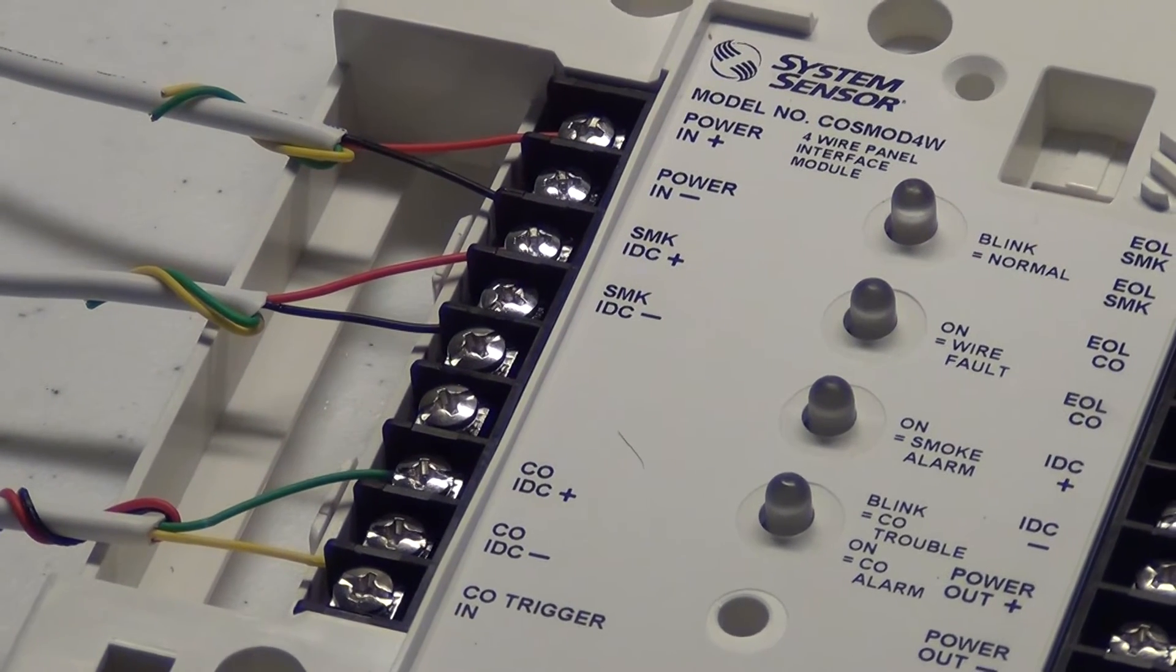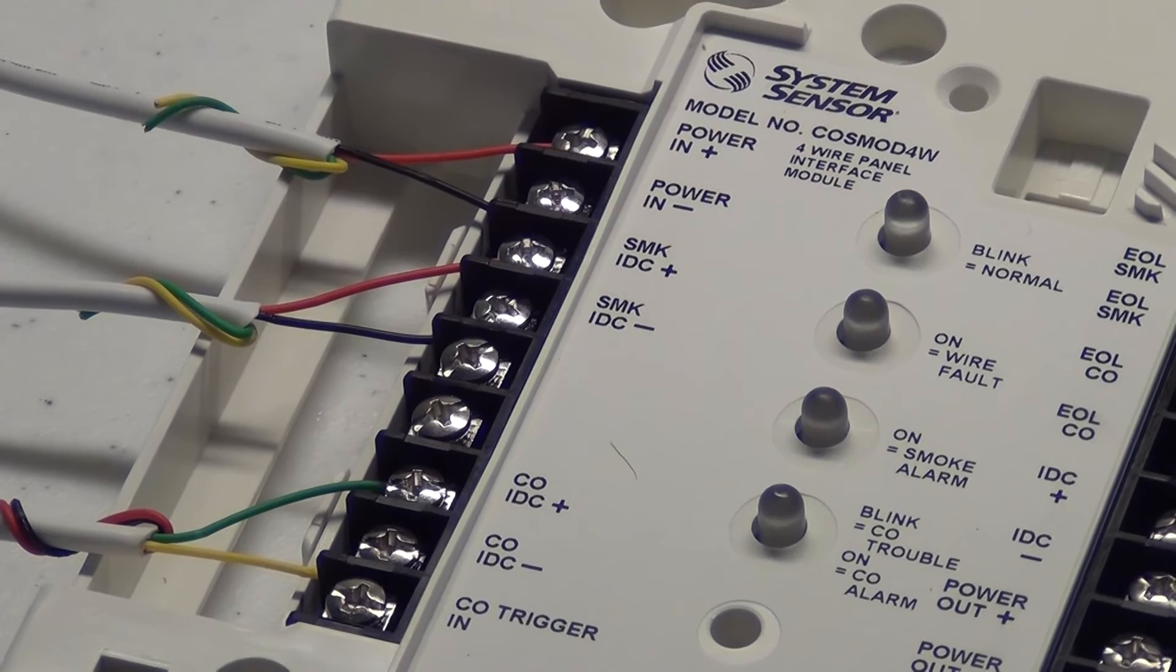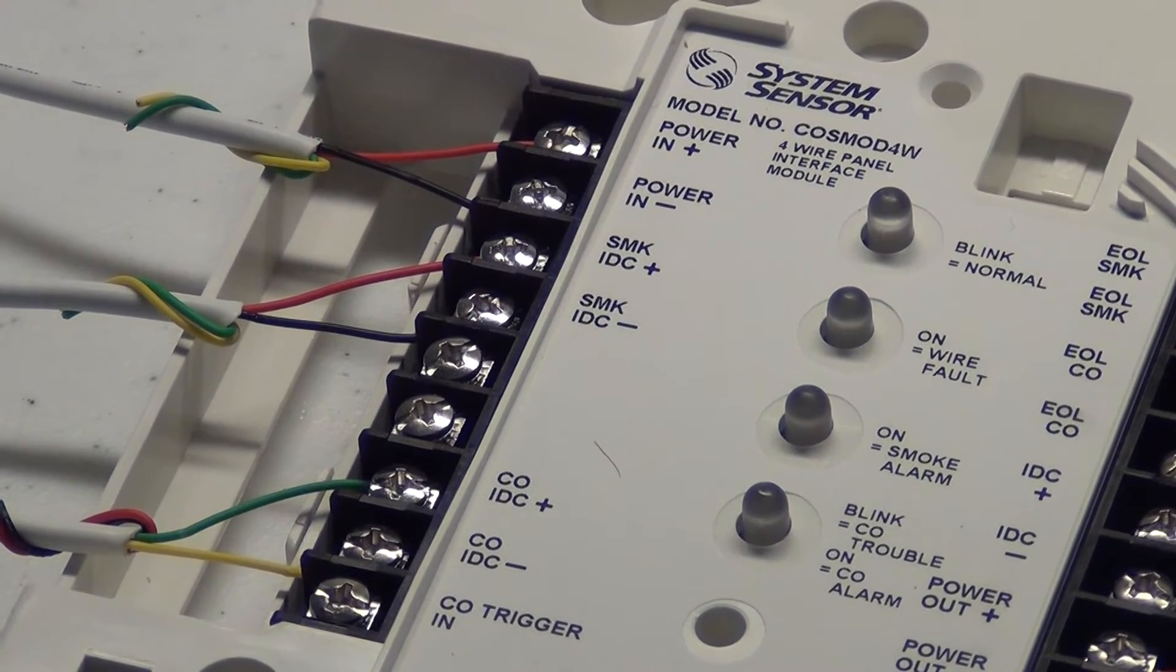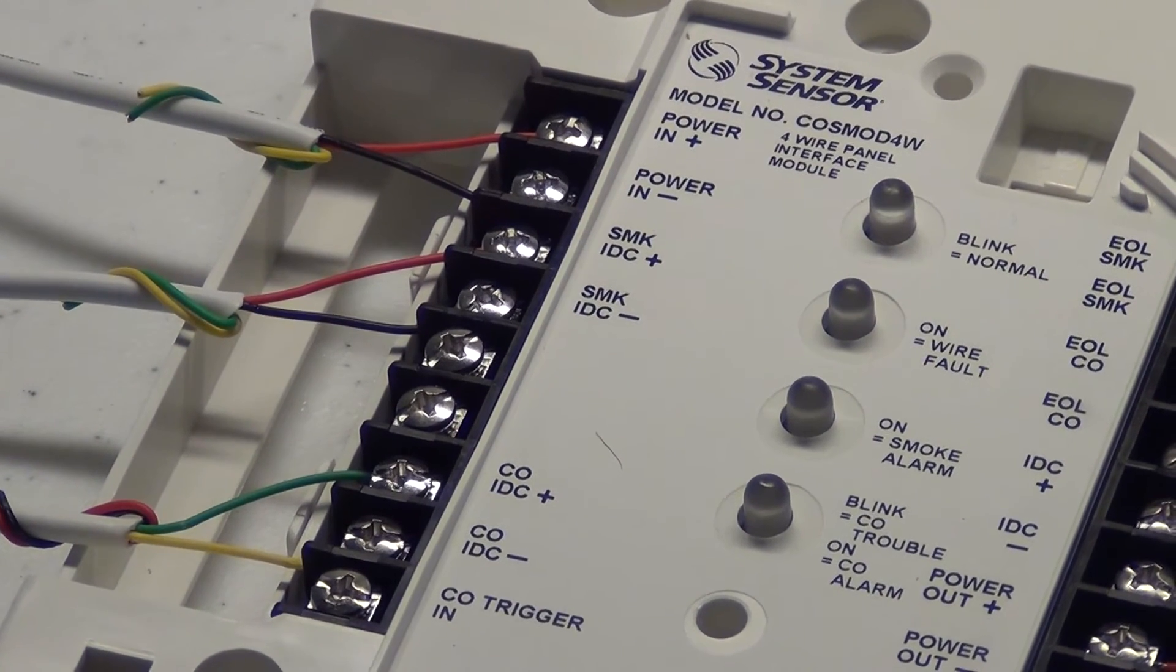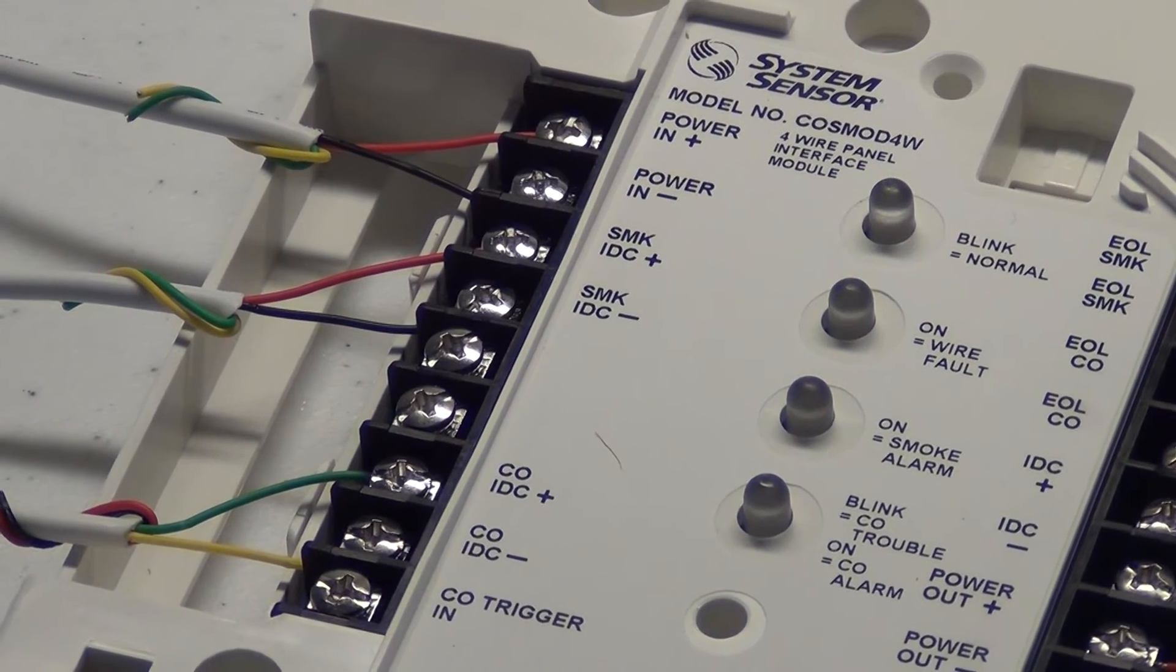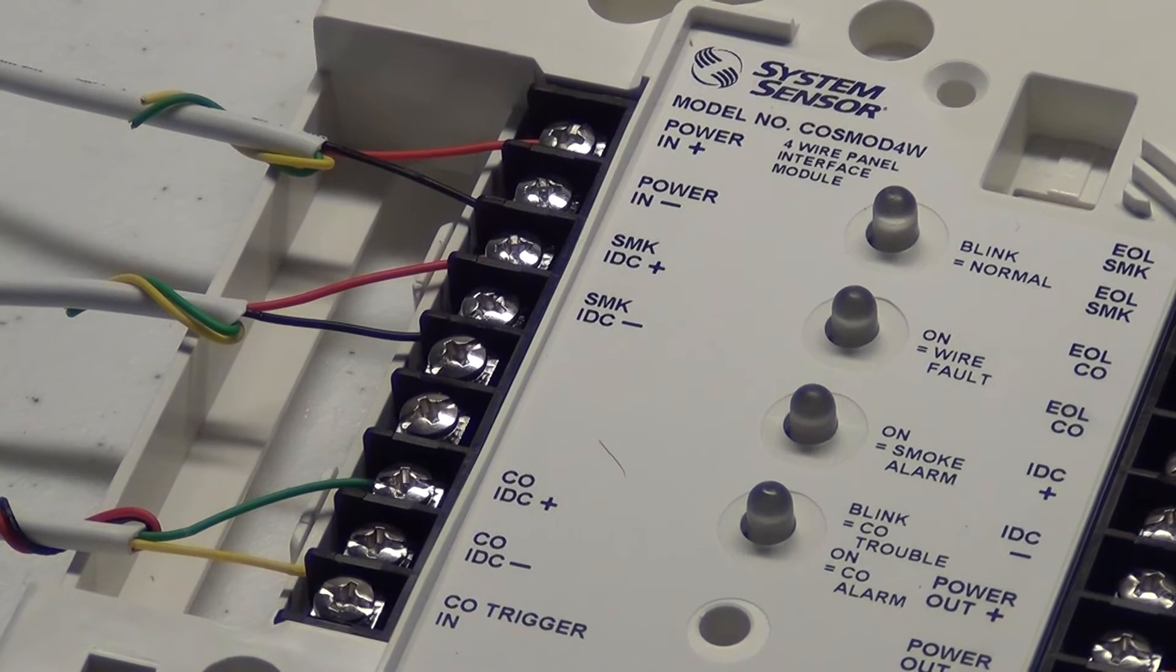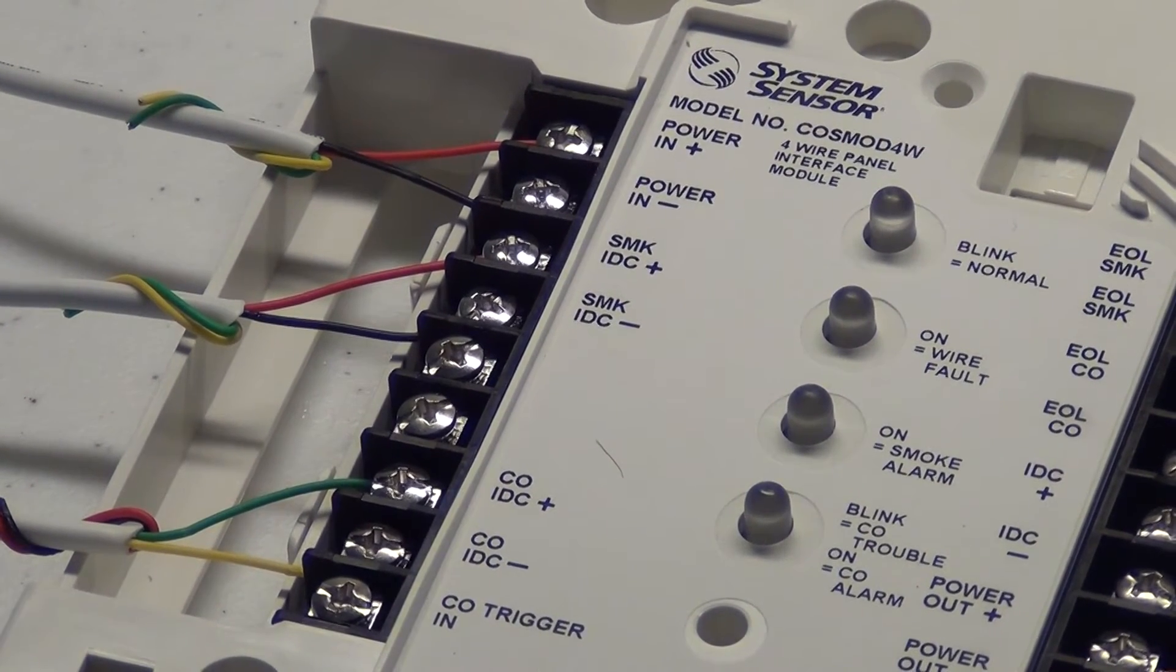Just remember that if you're using this on a Honeywell or a DSC you will have to connect the power wires to something on the board that is going to provide a reset for the smoke and the COs. On a DSC you will connect these into your PGM outputs on the board and do the programming for a smoke reset. This is a four wire hookup so you'll have to do programming for a four wire smoke reset.